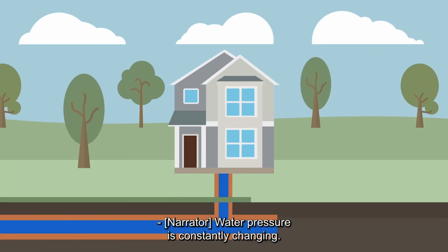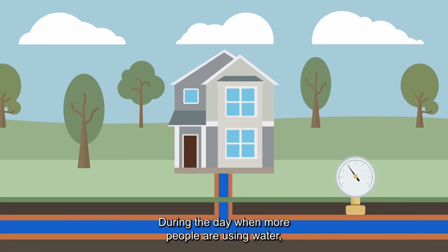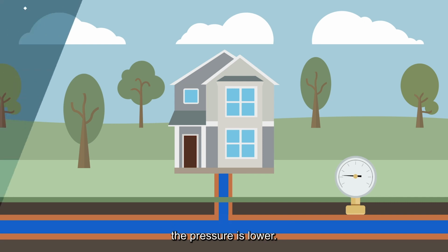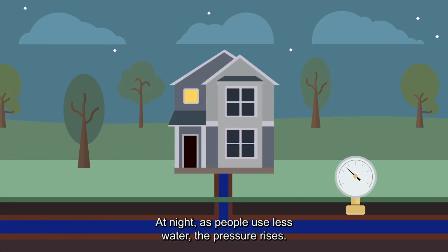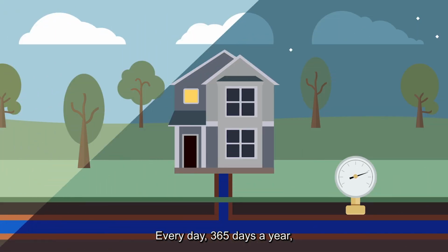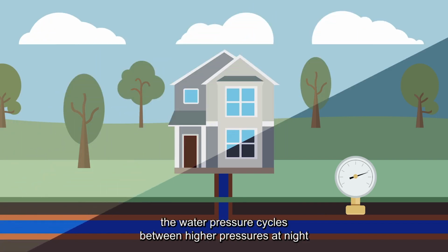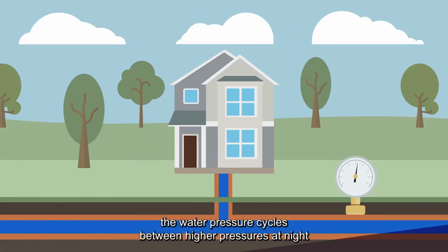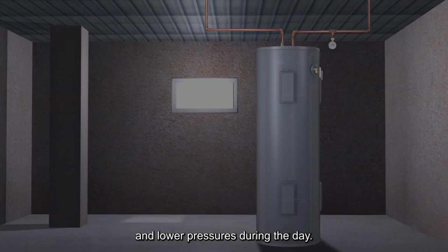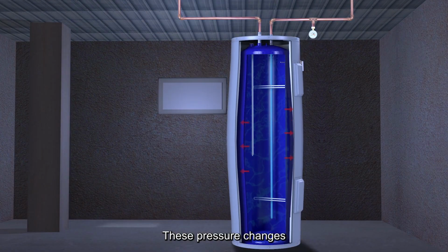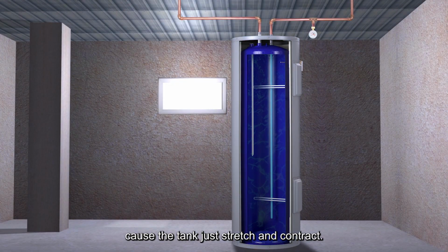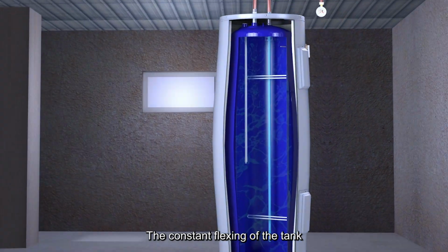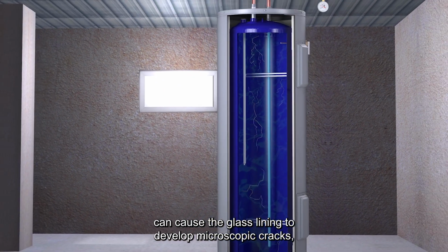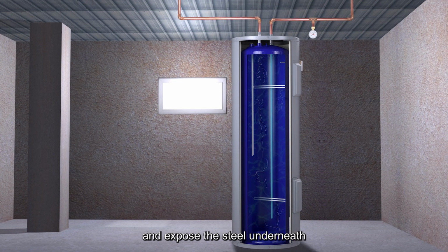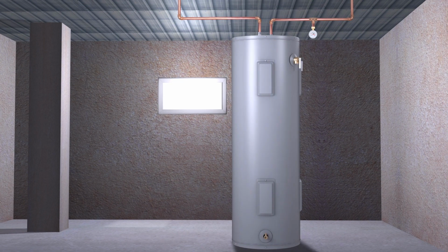Water pressure is constantly changing. During the day, when more people are using water, the pressure is lower. At night, as people use less water, the pressure rises. Every day, 365 days a year, the water pressure cycles between higher pressures at night and lower pressures during the day. These pressure changes cause the tank to stretch and contract. The constant flexing of the tank can cause the glass lining to develop microscopic cracks and expose the steel underneath to the corrosive effects of water.